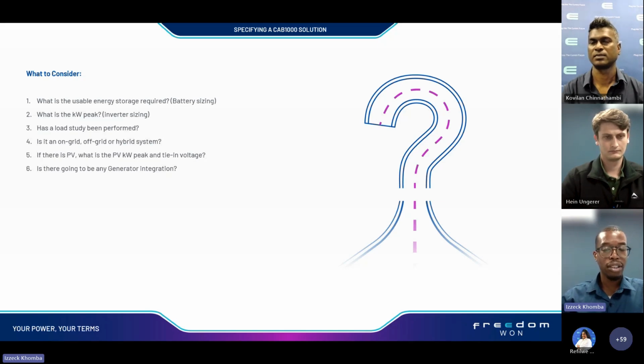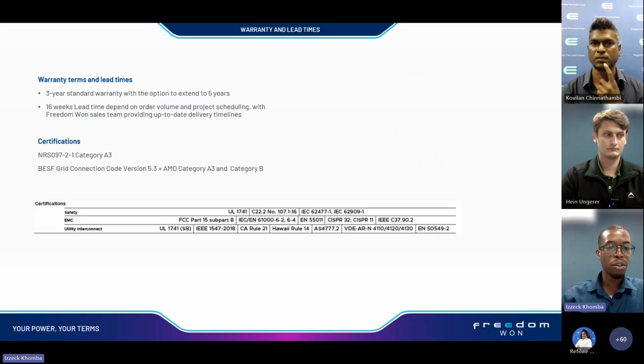Then generator integration can also be integrated on the output side of the inverter, meaning it will synchronize to the load bus of the inverter. In such a situation, a sync panel is required in order to control the generator as well, being integrated and using the inverter reference voltage to function. So these are very important key things that you need to consider when speccing a system to ensure that it's designed optimally and it functions in a manner which meets the client's expectations seamlessly.